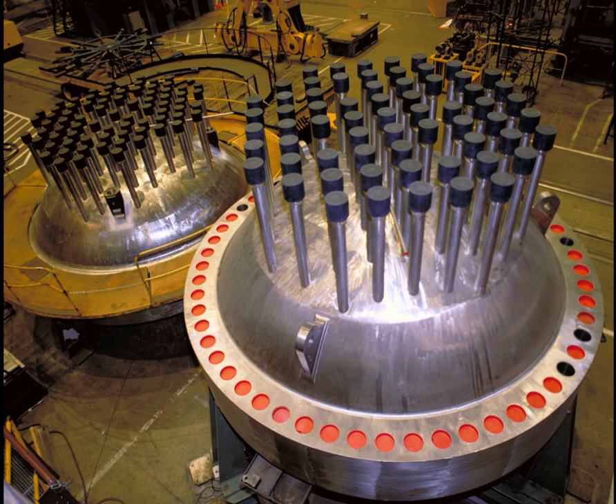The coolant water must be highly pressurized to remain liquid at high temperatures, requiring high-strength piping and a heavy pressure vessel, hence increasing construction costs. The higher pressure can increase the consequences of a loss of coolant accident. The reactor pressure vessel is manufactured from ductile steel but, as the plant is operated, neutron flux from the reactor causes this steel to become less ductile. Eventually the ductility of the steel will reach limits determined by applicable boiler and pressure vessel standards, and the pressure vessel must be repaired or replaced, which might not be practical or economic, and so determines the life of the plant. Additional high-pressure components such as reactor coolant pumps, pressurizer, steam generators, etc. are also needed, increasing the capital cost and complexity of a PWR power plant.